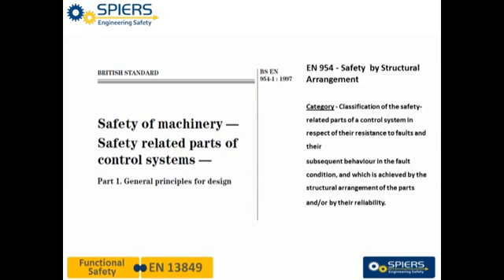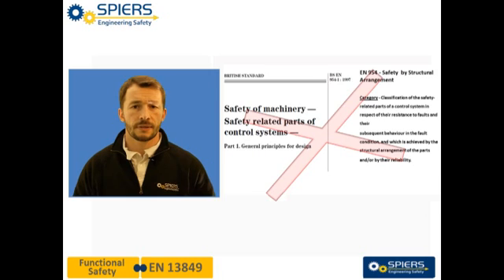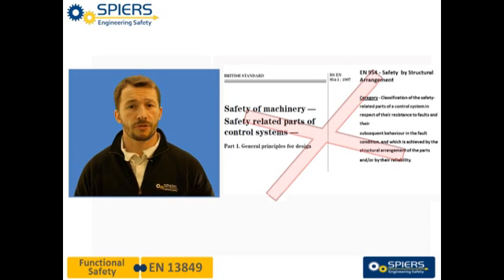EN 954 focused heavily on the structure of the safety related circuit. This has now been superseded by EN 13849, which has reduced this emphasis on structure and introduced the need for the reliability of the safety circuit to be considered. This has increased the burden upon safety component manufacturers to provide suitable failure data and support in the applications in which their components are used.